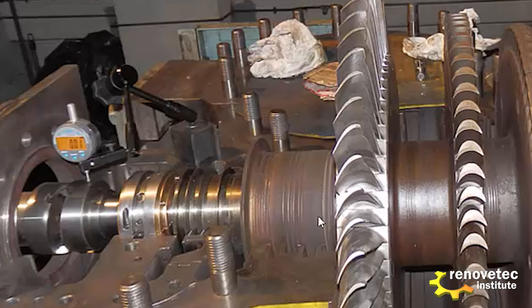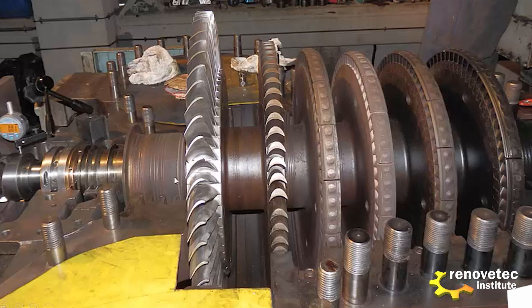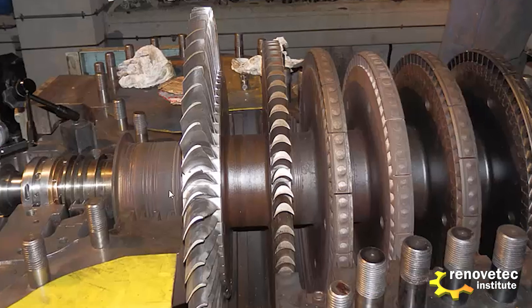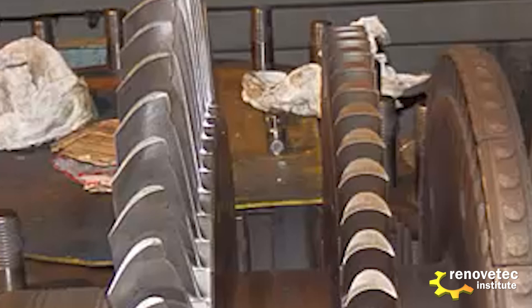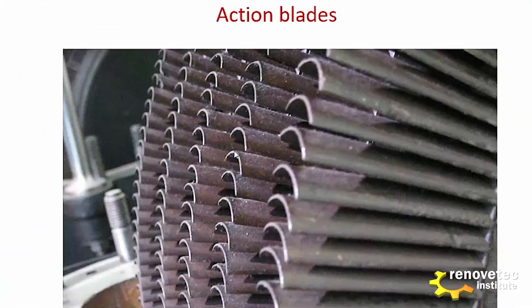The last row of blades is the most delicate part of a steam turbine. In this picture we can see that the blades are damaged — we can recognize a very common damage provoked by the inlet of drops of water. This is an action turbine. The typical shape of the action blades is because the steam pushes and impulses the blades.